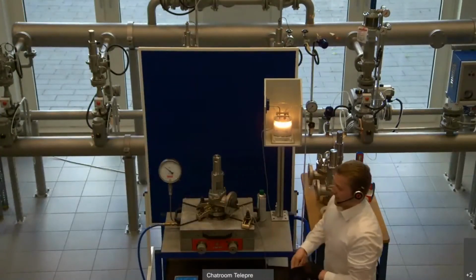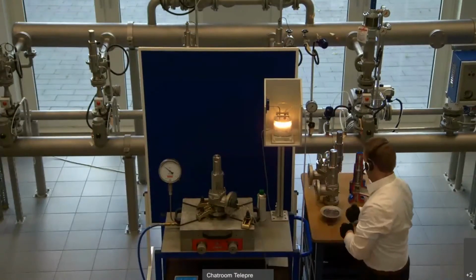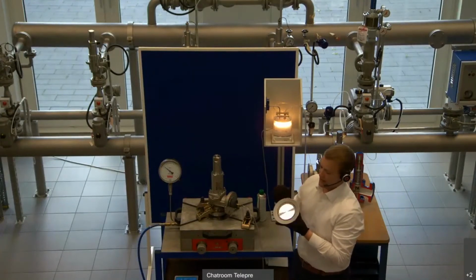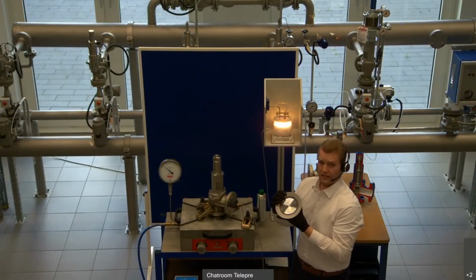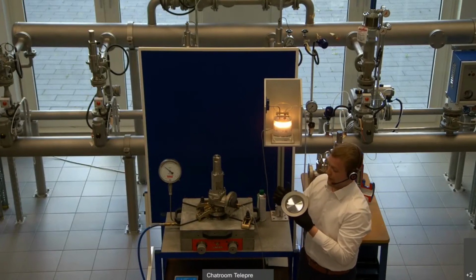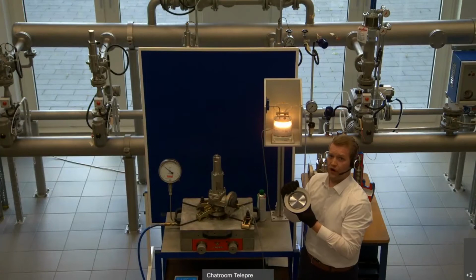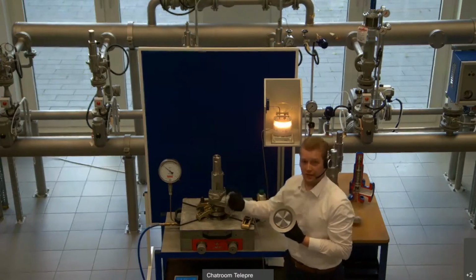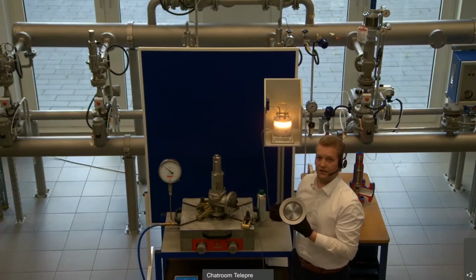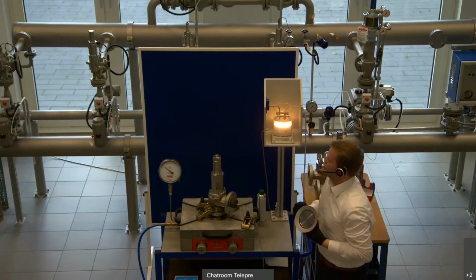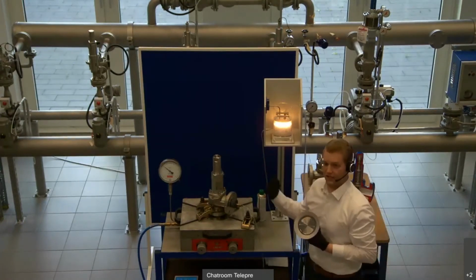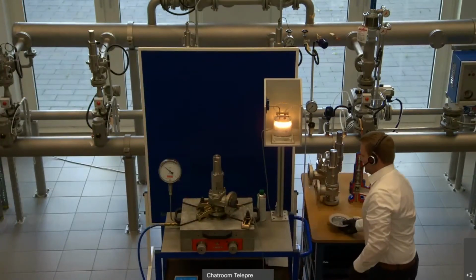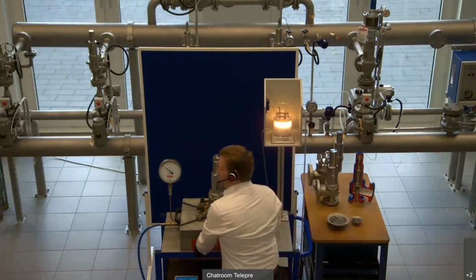What stands behind this is what we call LESER nano tightness. For LESER nano tightness, the material is very important, for example the structure of the tightness area and the hardness. LESER invests millions of euros in special lapping machines, and so we called it LESER nano tightness. Here you see for a metal to metal sealing we have 0 bubbles in 10 seconds, so it is very tight. This was our first live demonstration, and now I want to go on to another safety valve.